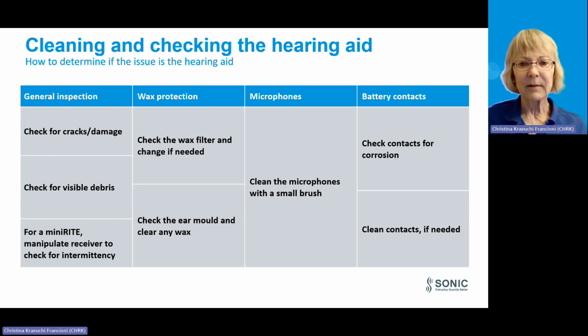Battery contacts. If a hearing aid often runs out of power, it's not necessarily because it needs a new battery. Check the charging contacts on the hearing aid for dirt and corrosion and clean with a cloth if needed. Also, for detailed cleaning instructions, please refer to the instructions for use manual associated with that specific hearing aid model.